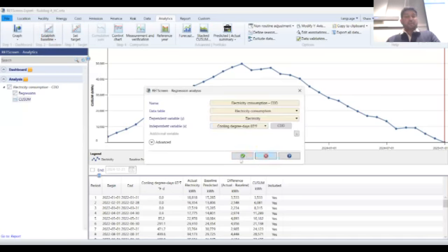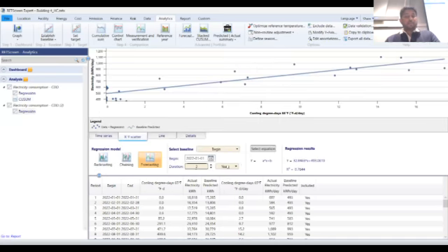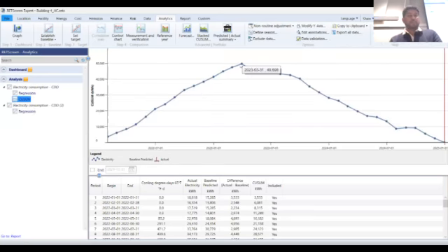Again, the same, 65. Now, in the baseline, select baseline column, I am going to end the baseline in 15 months. Because if you remember, in March 2023 is when the graph started going down. And I can go back to show you. So March 2023 is when the chart started going down, which means I'm saving energy starting from those points. And there are 15 months leading up to March 2023.